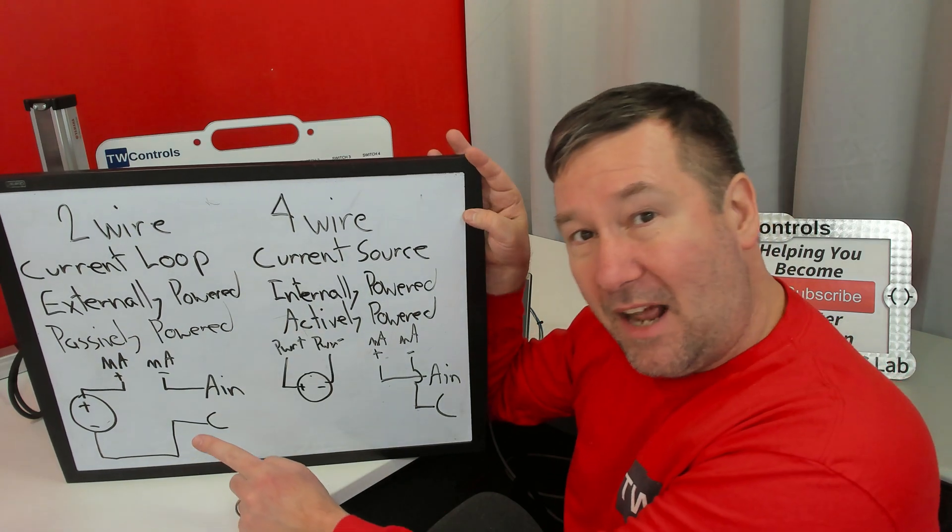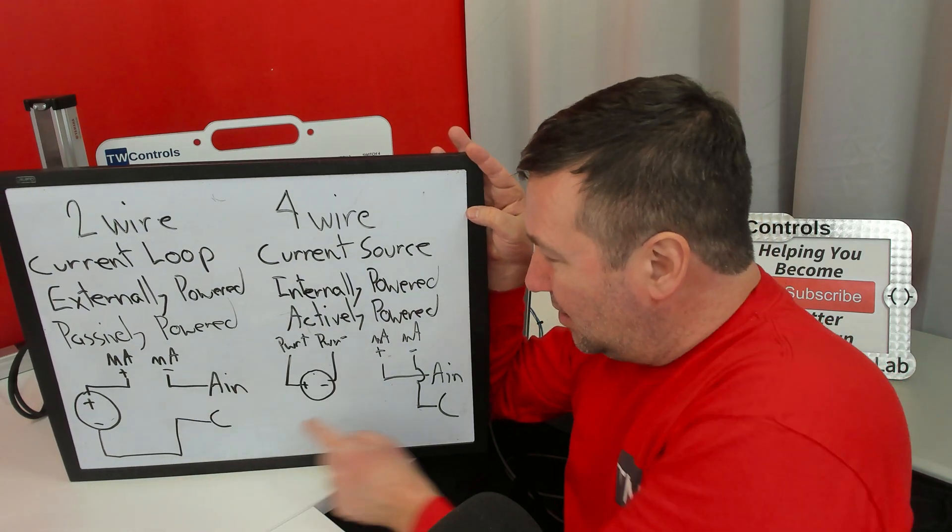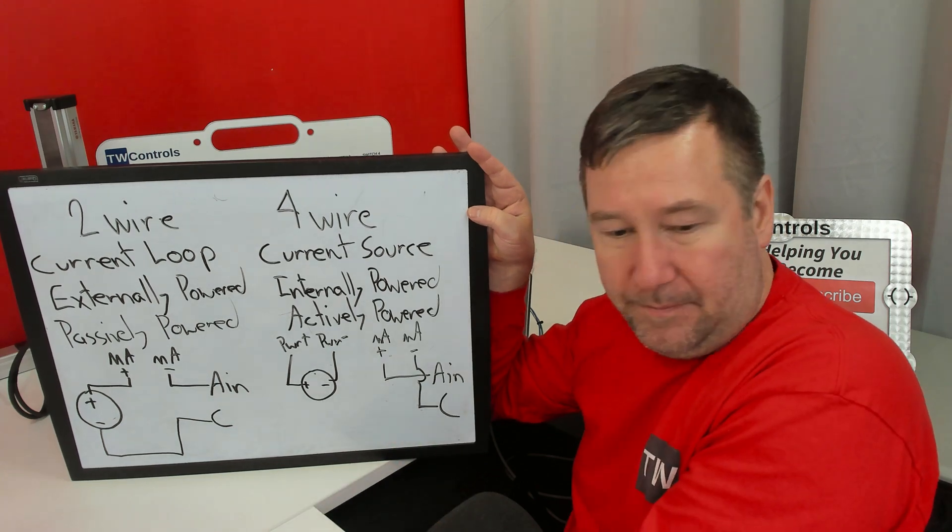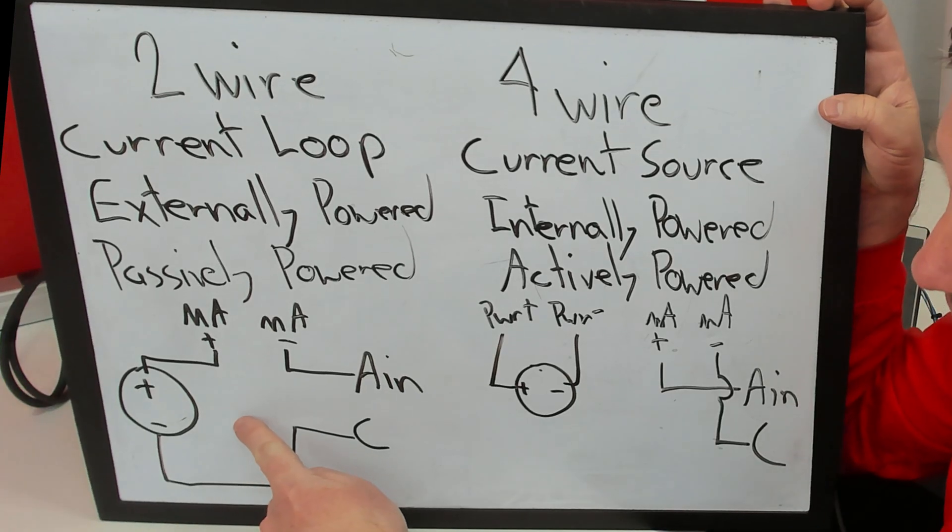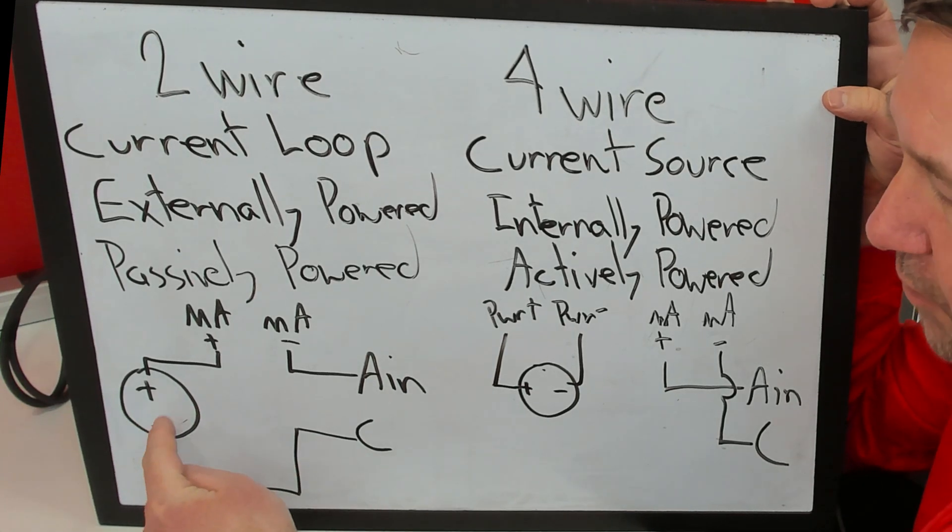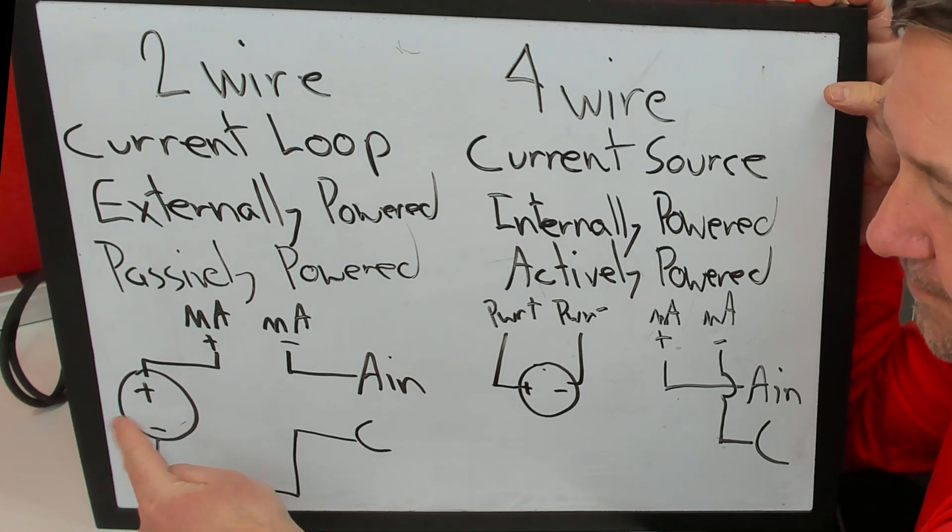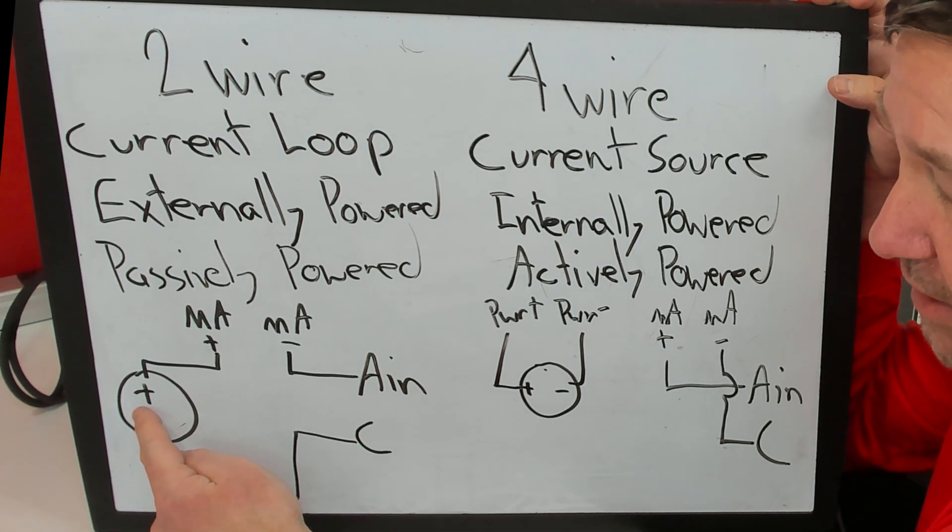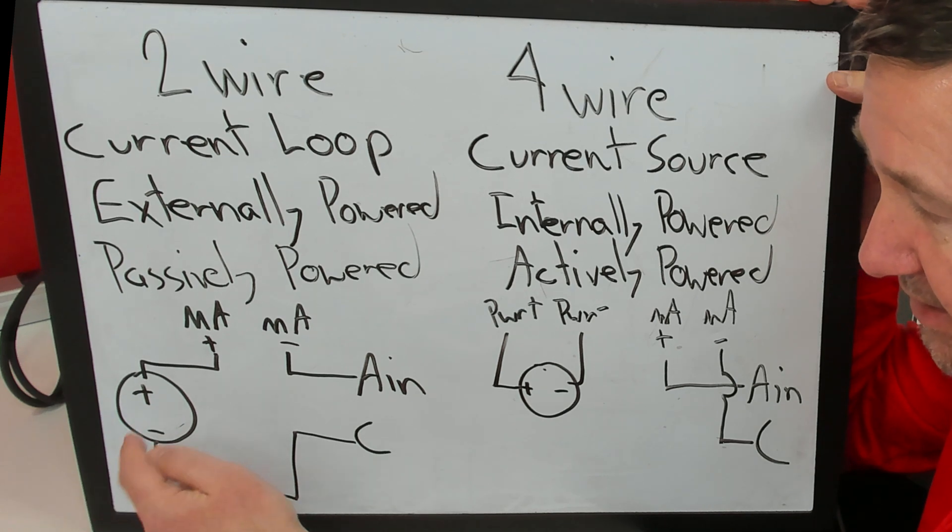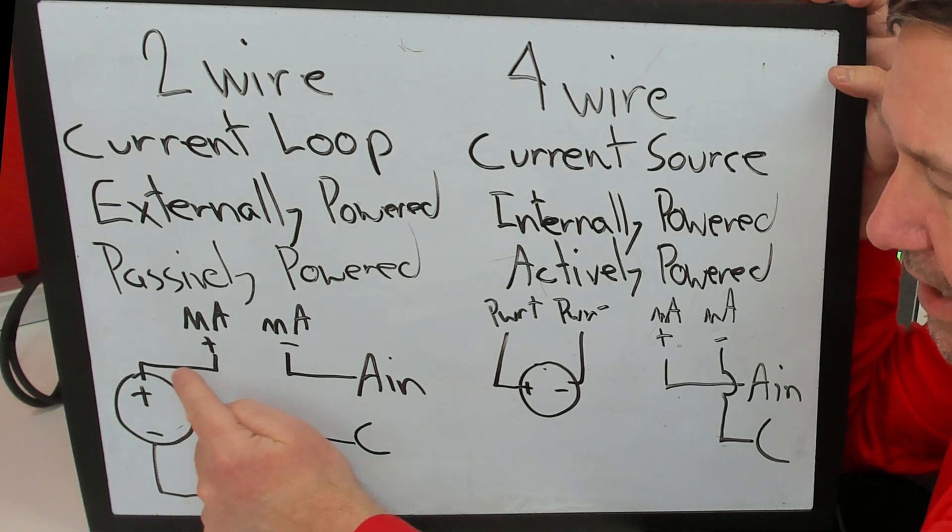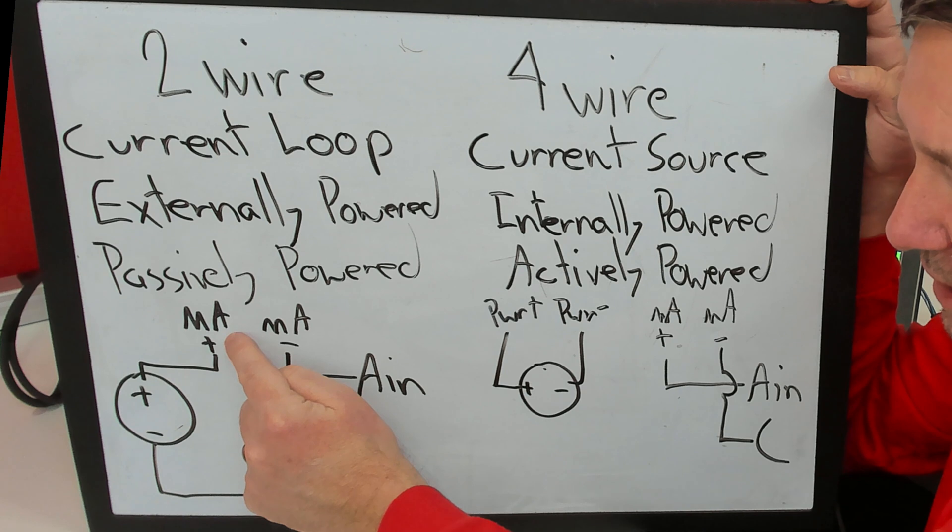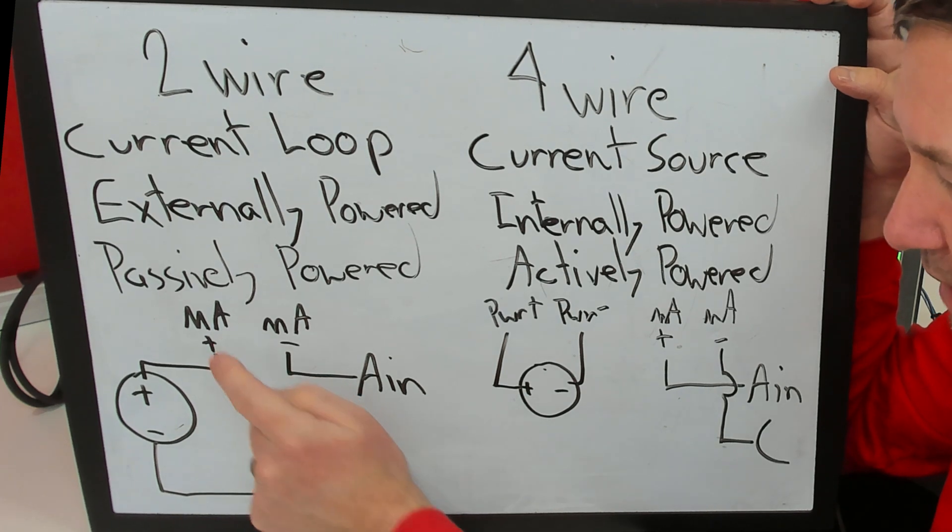Now let's talk about how we're wiring these two, because here's where the confusion really comes in. In the case of a two-wire device, we need an external power supply. This will very typically be 24 volt DC, but it could be something else. And we're going to feed positive power up to the milliamp plus of our sensor.